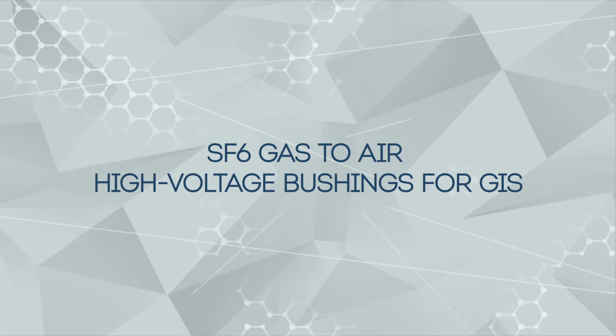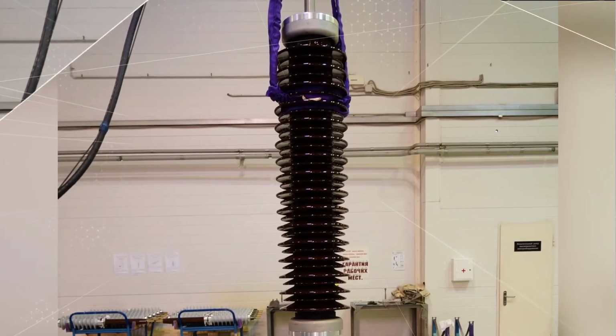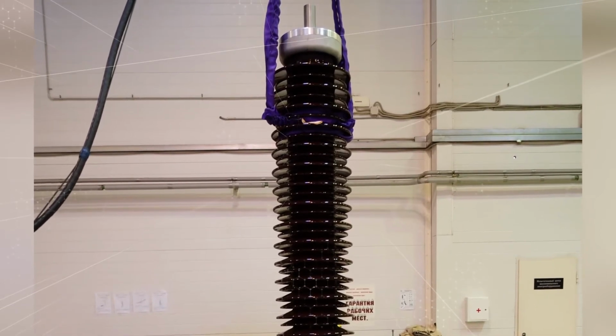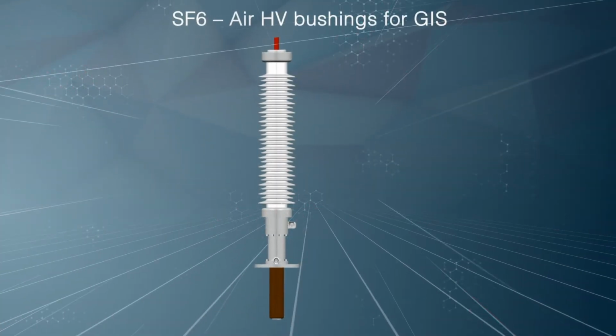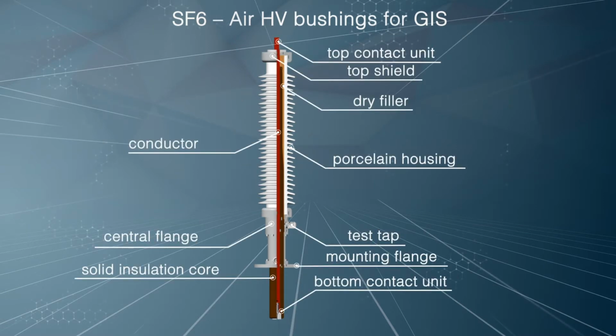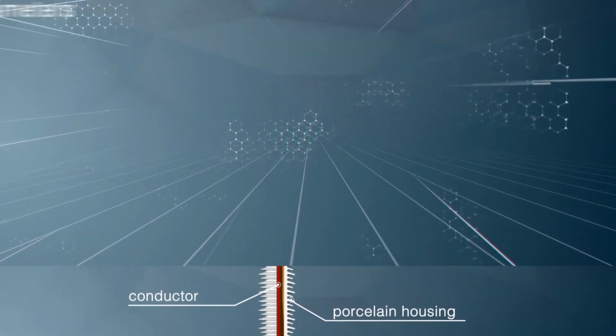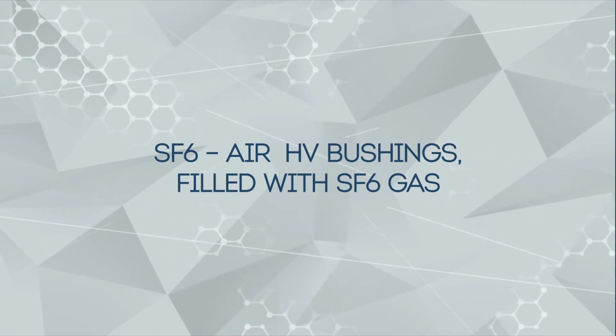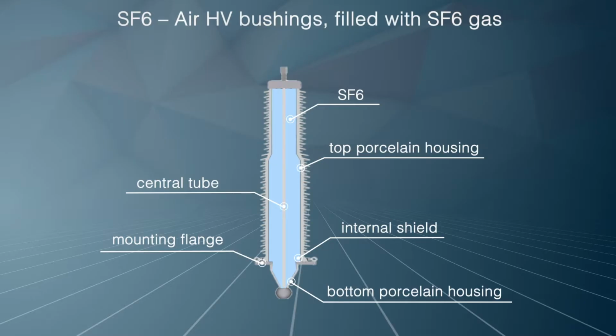SF6 gas to air high voltage bushings for GIS. This group includes special bushings intended for connection of GIS to power lines. In operation, the bottom part of the bushing is positioned inside the GIS or transformer, in the gas medium, while its top part is in the open air. SF6 air HV bushings are filled with SF6 gas. Their difference is in the simplicity of construction. No insulation core, no equalizing or condenser liners, no need in test tap. However, in order to create an enclosed volume, the bushing has a bottom porcelain housing. To equalize the electric field inside the bushing in the grounded flange area, they use an internal shield.